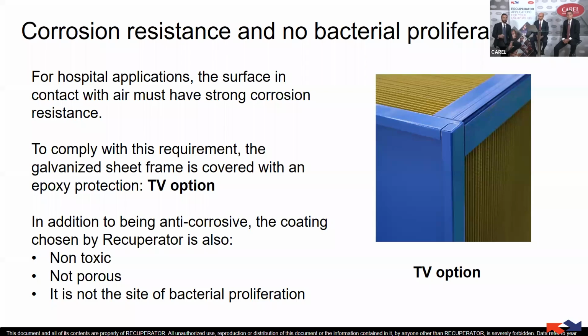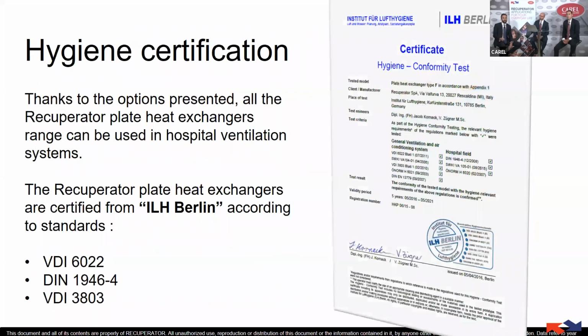The epoxy protection that we use is not toxic, not porous, and easy to clean because it's smooth. In this way, it's also not a place for bacteria proliferation. So we fulfill the characteristic of being cleanable, but also the characteristic of avoiding corrosion in any way. All these characteristics are defined and combined together by a conformity certificate delivered by a third-party laboratory, which explains that the heat exchanger is suitable for hygienic application.